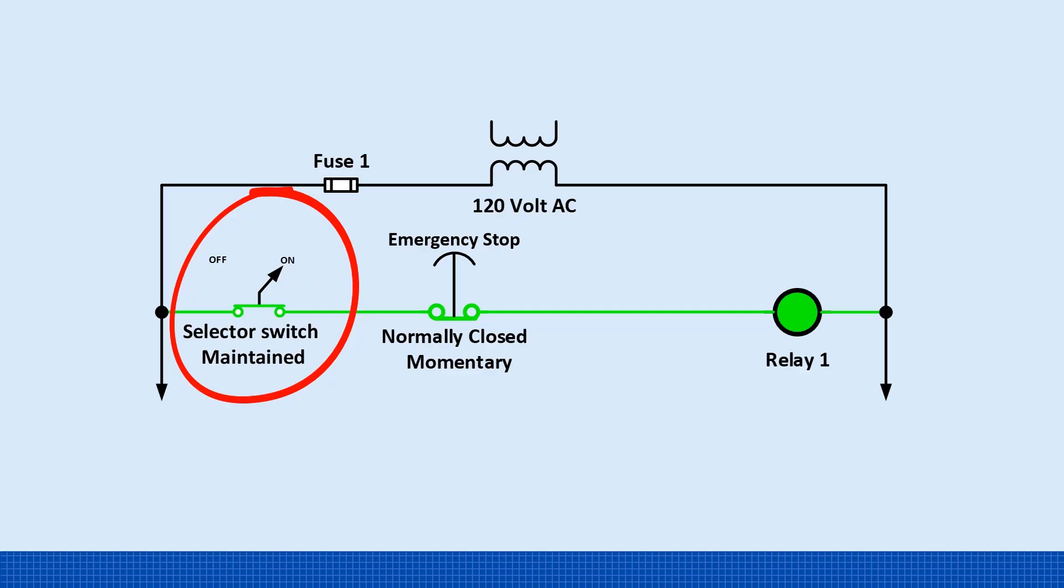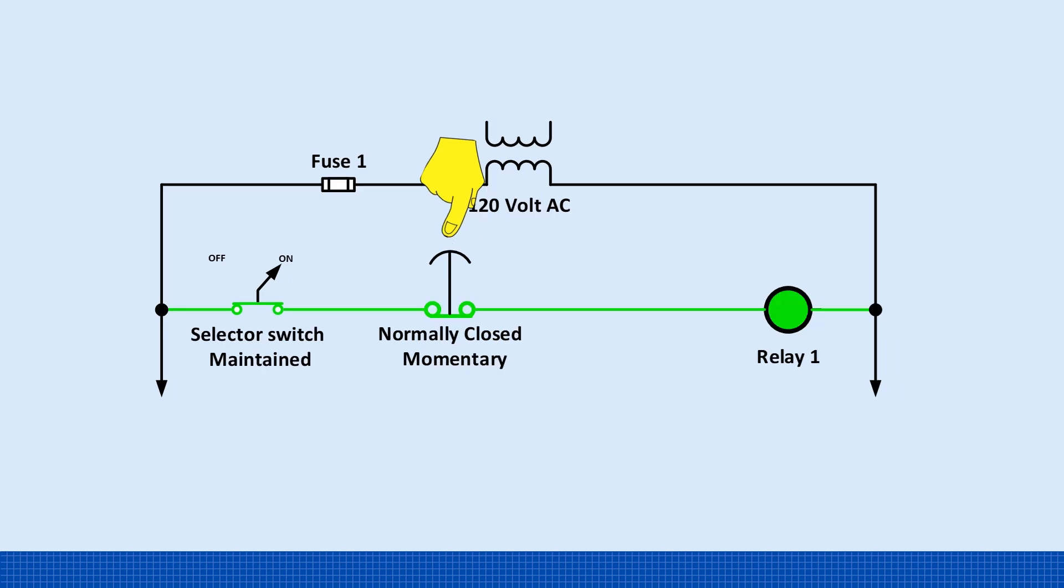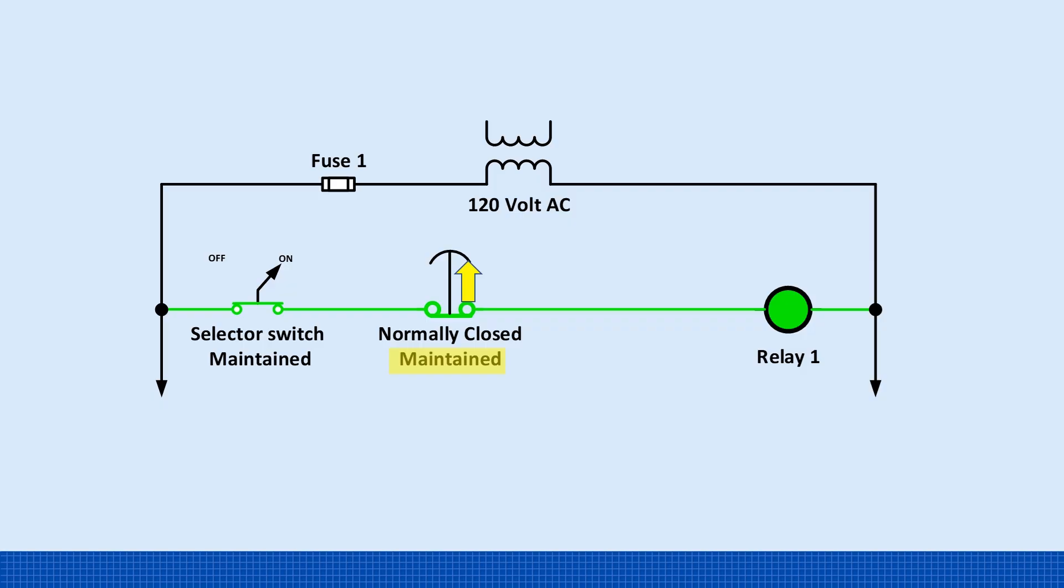It will remain on as long as the circuit stays closed. Now, if the emergency stop is pressed and held, the circuit opens and relay one de-energizes immediately. But the moment you let go of the emergency stop, it returns to its normally closed state, completing the circuit, and relay one turns back on. Even with a maintained emergency stop switch, as soon as it's turned back to its normally closed state, the circuit is restored and relay one energizes.